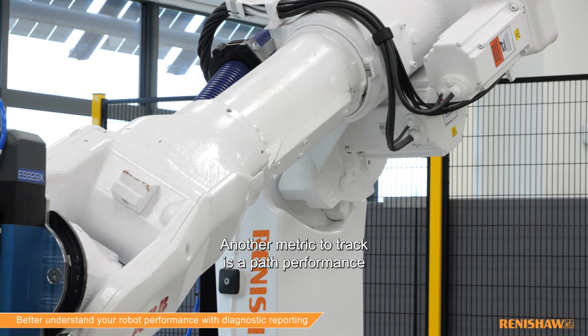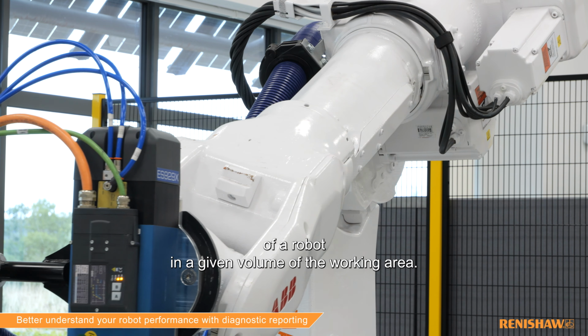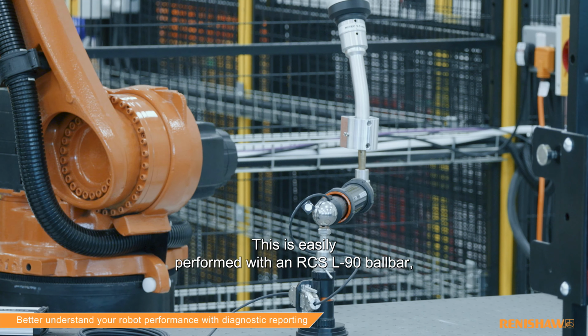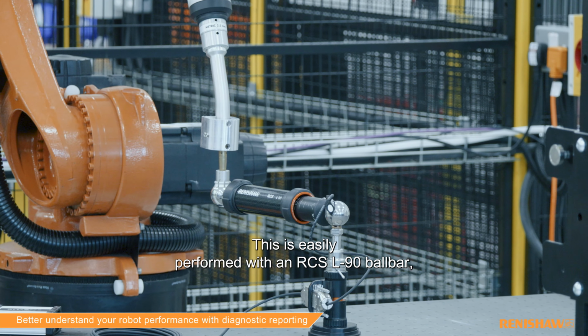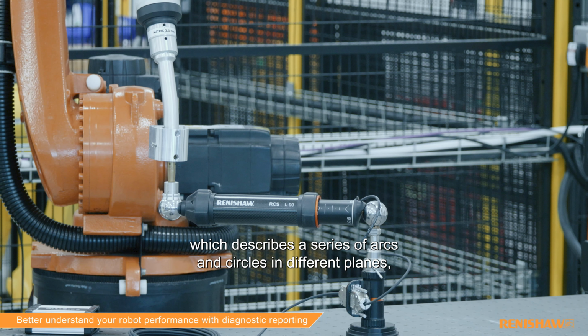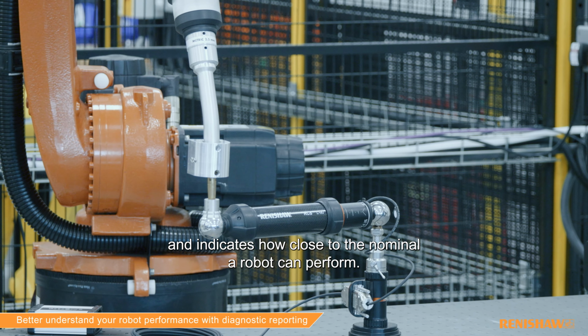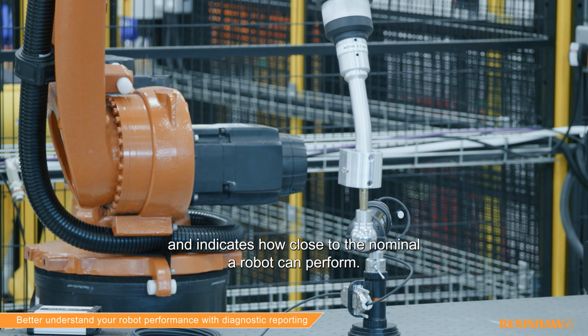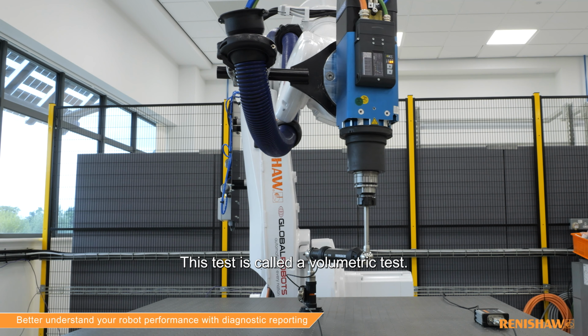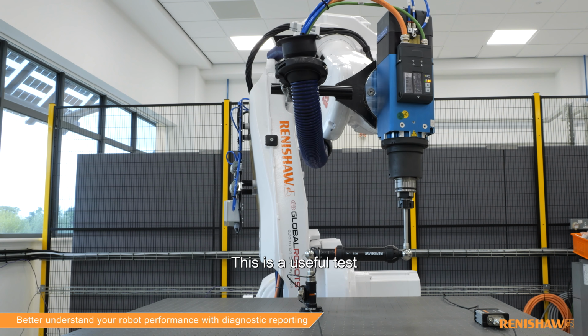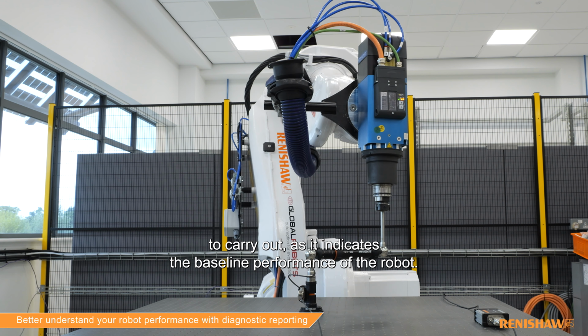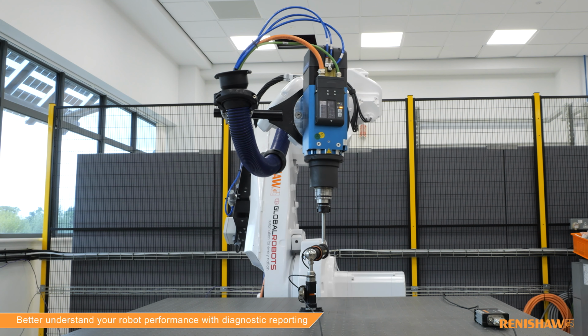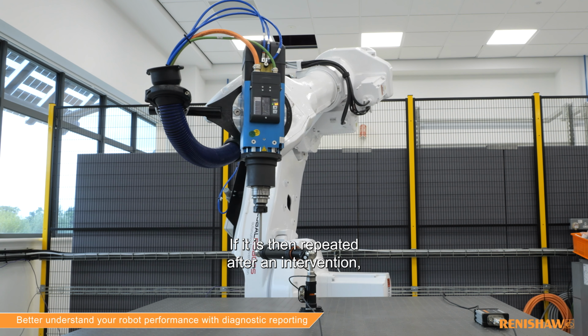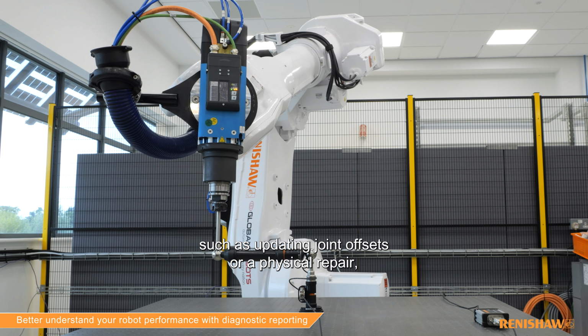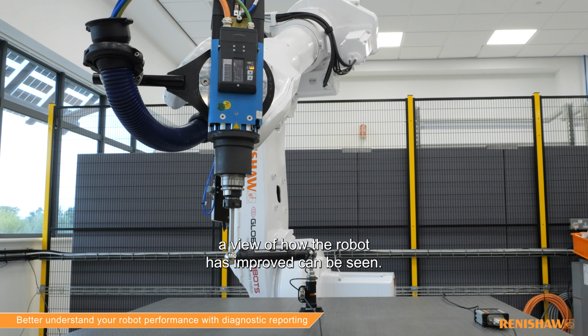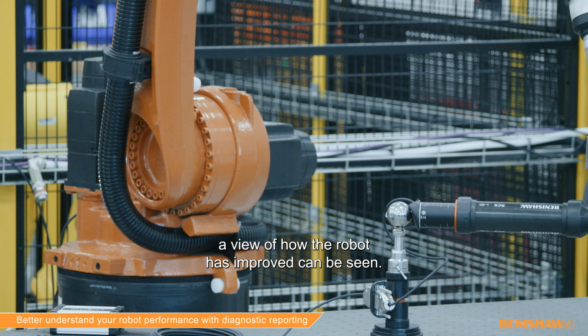Another metric to track is the path performance of a robot in a given volume of the working area. This is easily performed with an RCS L90 ball bar, which describes a series of arcs and circles in different planes and indicates how close to the nominal a robot can perform. This test is called a volumetric test. This is a useful test to carry out as it indicates the baseline performance of the robot. If it is then repeated after an intervention, such as updating joint offsets, or a physical repair, a view of how the robot has improved can be seen.